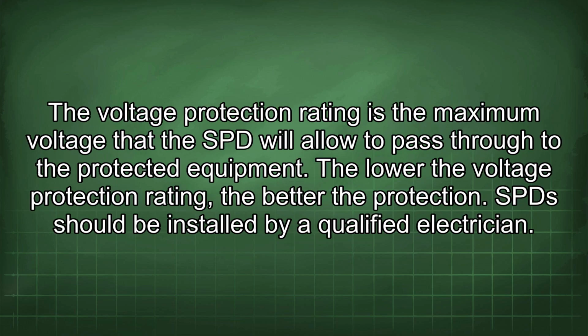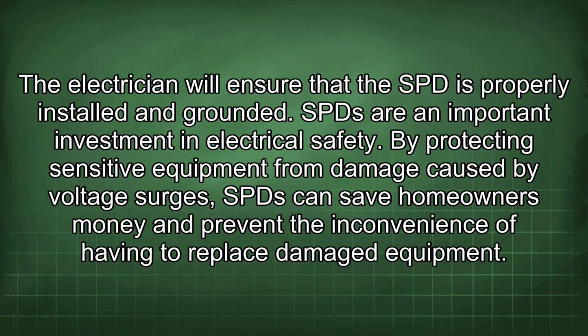The voltage protection rating is the maximum voltage that the SPD will allow to pass through to the protected equipment. The lower the voltage protection rating, the better the protection. SPD should be installed by a qualified electrician. The electrician will ensure that the SPD is properly installed and grounded. SPD are an important investment in electrical safety. By protecting sensitive equipment from damage caused by voltage surges, SPD can save homeowners money and prevent the inconvenience of having to replace damaged equipment.